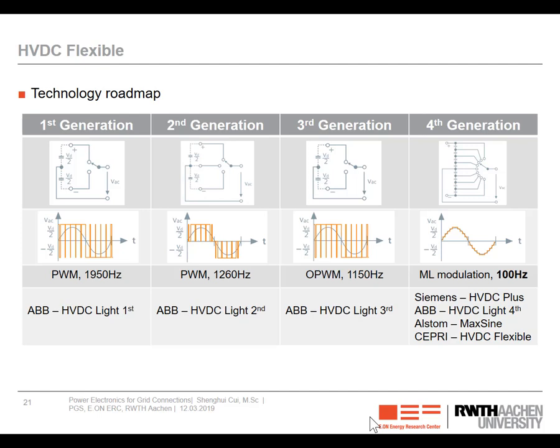There are mainly two reasons behind it. One is that when the third generation technology was commercialized, almost in 2005, the performance of power semiconductor devices was much, much better than in the earlier era. And at this time, there was a so-called optimized PWM technology invented by a German professor, which can further decrease the switching frequency while keeping all the harmonic contents within regulation. So when the third generation technology is applied, you can have much better efficiency. For the fourth generation, they moved to the multilevel converter, called the modular multilevel converter.